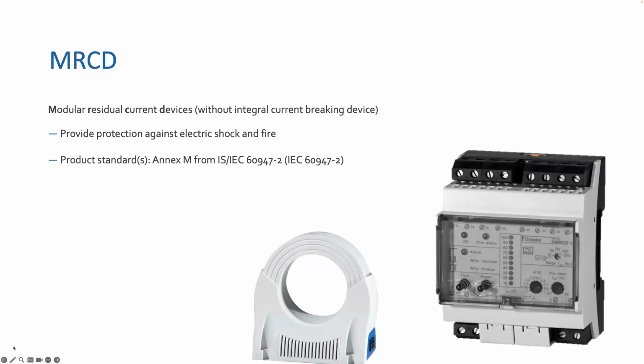See, it's a very good question. I'll go back to the slide that Gerard has shared. I'll share my screen. When you have an MCCB without earth leakage tripping characteristics, you need to use what is called an MRCD. Now, you cannot just use any ELR with a CBCT, and you cannot use an RCM either. The device, the CBCT and the relay together have to conform to Annex M of IEC 60947-2. Only then can you use it for earth fault protection. Otherwise, if it is some generic ELR or an RCM, a residual current monitoring device, that device cannot be used for protection. Which is why this standard, IEC 60947-2, comes in, and products specifically designed for protection are manufactured under this standard. Only these products can be used.